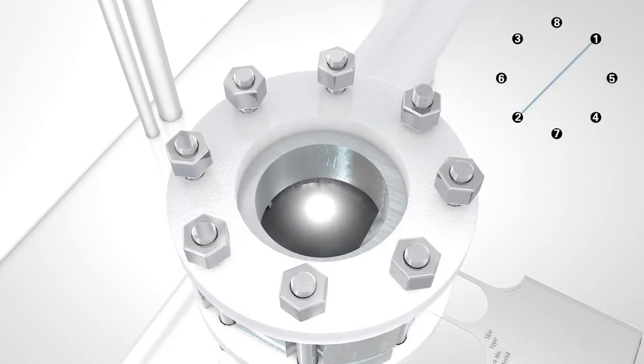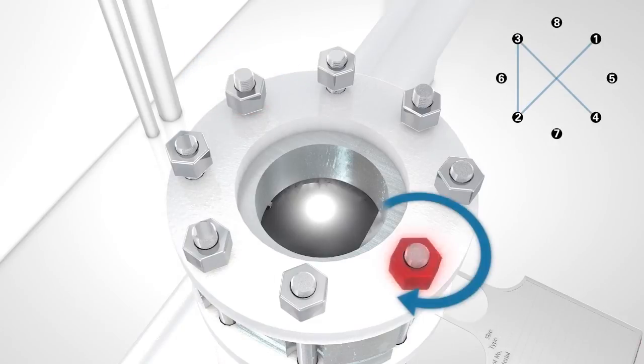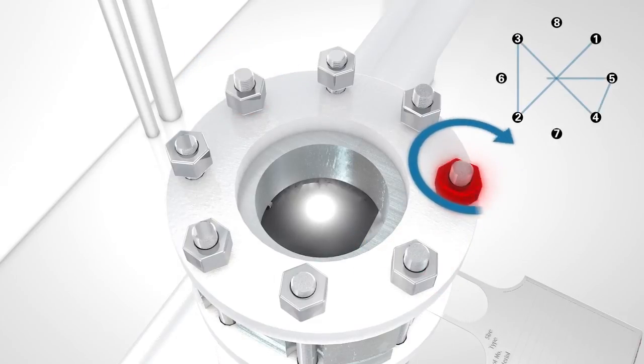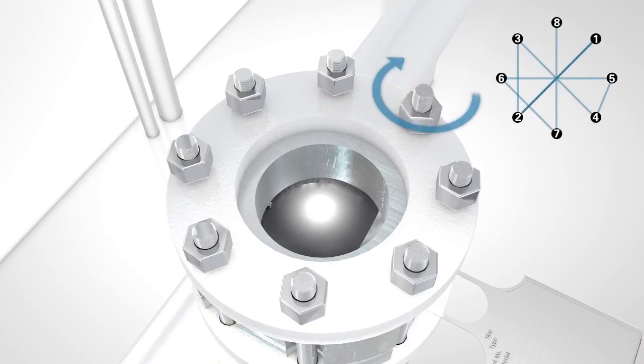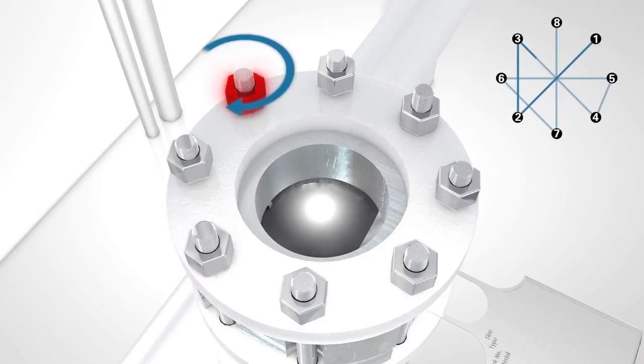Using a criss-cross pattern, apply torque in 25% increments. For example, if the required torque is 100 ft-lbs, torque would be applied in 25 ft-lbs increments using the criss-cross pattern.